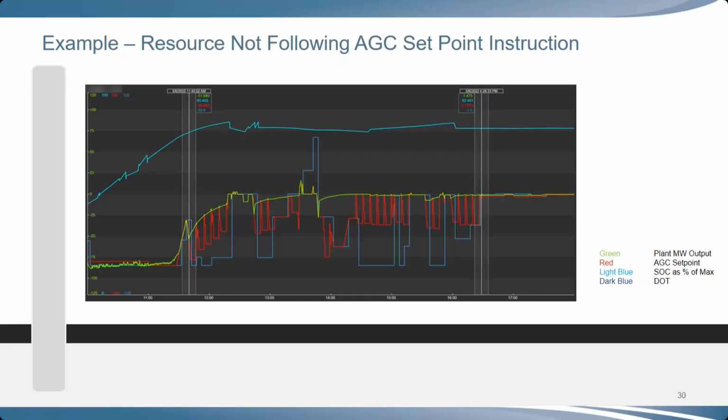The second thing is if it is above that, we'll submit an outage ticket, but there's a lag once it's approved before it can actually show up in the market, about 37 minutes or so. And so that can be another reason there might be a little bit of a separation from a DOT we receive versus what we can physically respond to. I'm just trying to chunk that out, these two pieces, a lower unavailability versus a lag in the outage that you would be expecting, and how you want us to communicate back in those instances. Does that make sense?